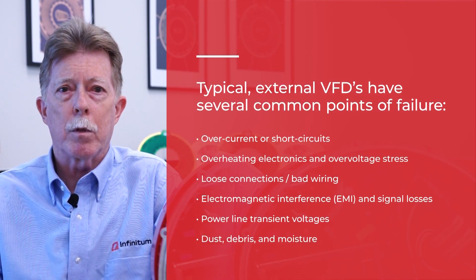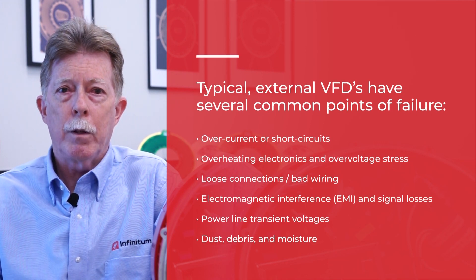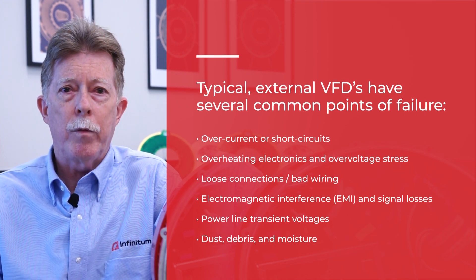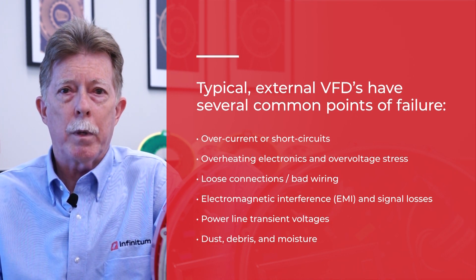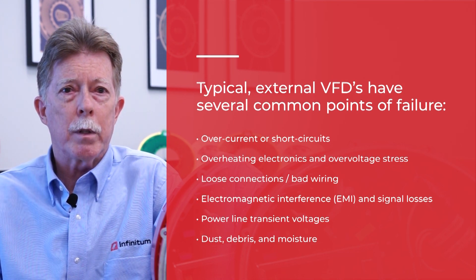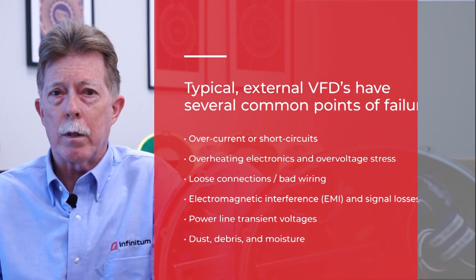While many other motor manufacturers sell drives separate from the motor, Infinitum VFDs are integrated with the motor, forming a motor drive system. Typical external VFDs have several common points of failure: overcurrent or short circuits cause damage to the power electronic switches; overheating electronics and overvoltage stress; loose connections or bad wiring between the VFD and motor; electromagnetic interference (EMI) and signal losses on communication links; power line transient voltages or high components of harmonics in the power line. Even dust, debris, and moisture can build up in the VFD causing damage.